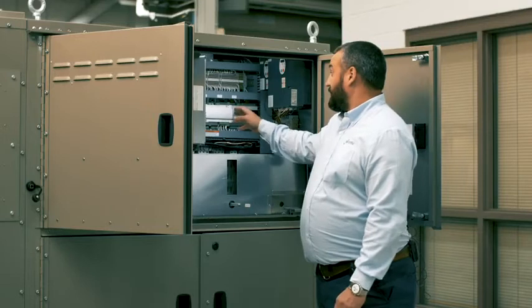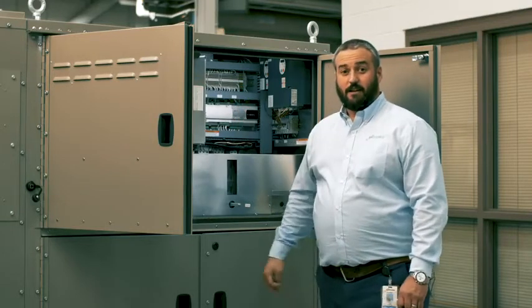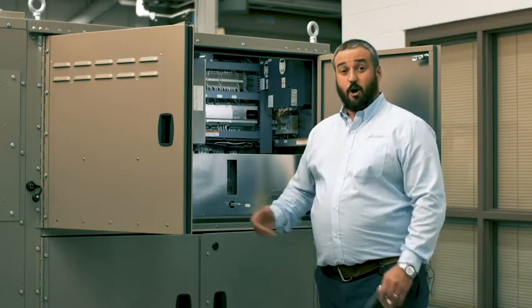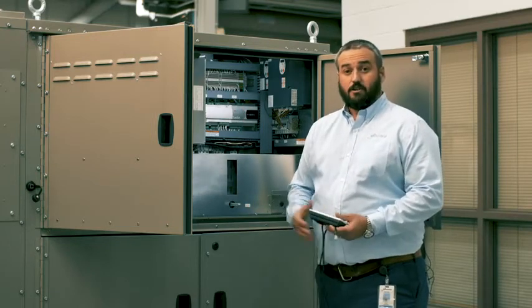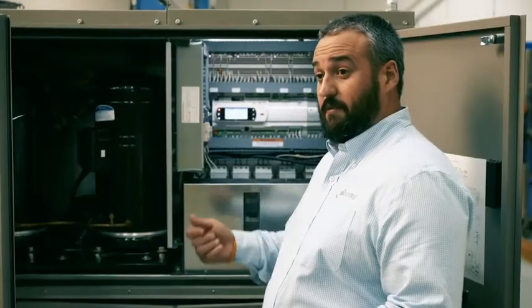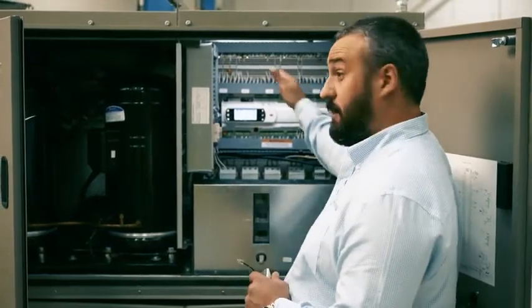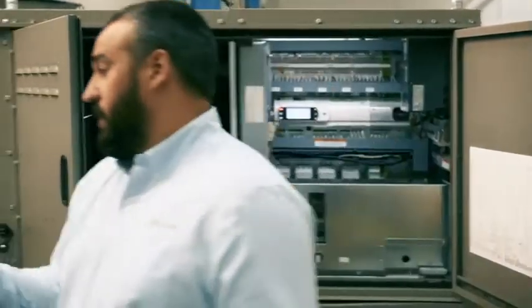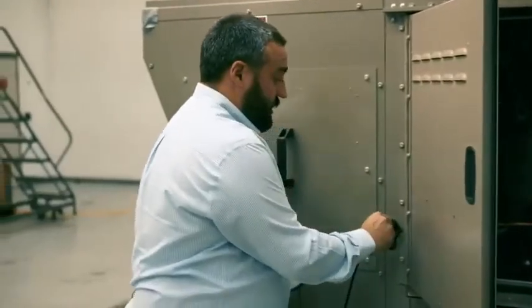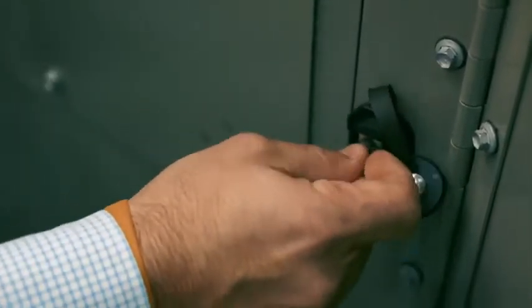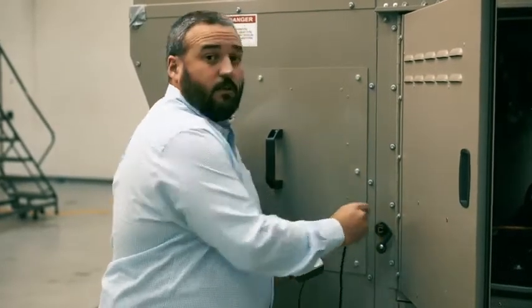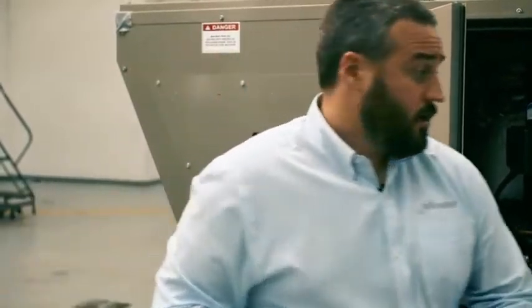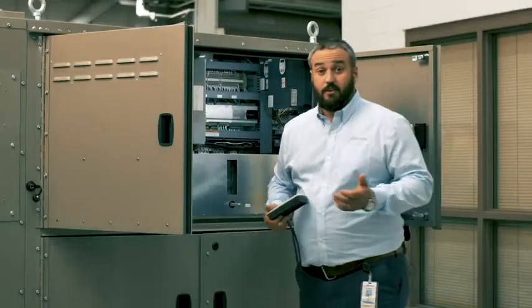Because the controller's mounted in a high voltage panel, we've added the option for a remote port to plug in your display. The reason we've done this is because the unit would have to be switched off by the isolator to be able to plug into the controller. This is really nice for a service engineer because he has the option to connect into the unit and read all the values without having to shut the unit down. This option isn't required on a D cabinet because we've added a 24-volt control panel which houses the controller. So you don't need to worry about that on a D cabinet.